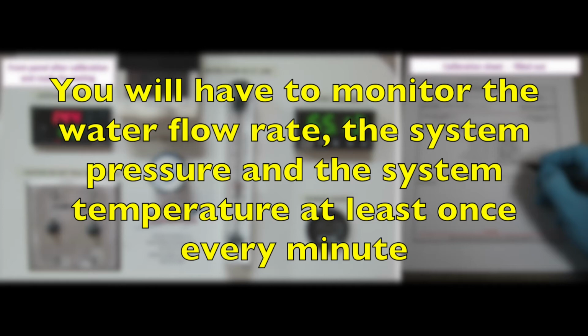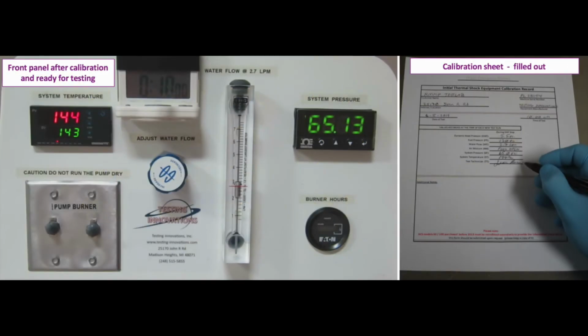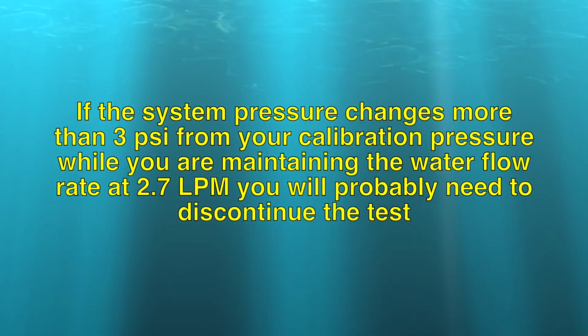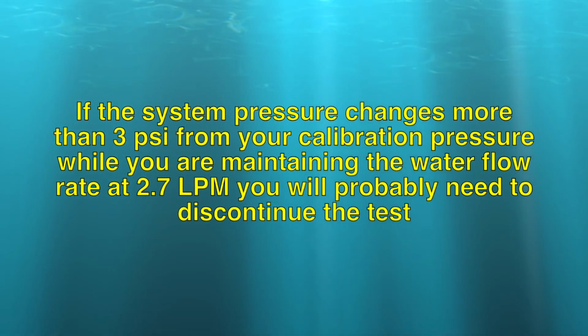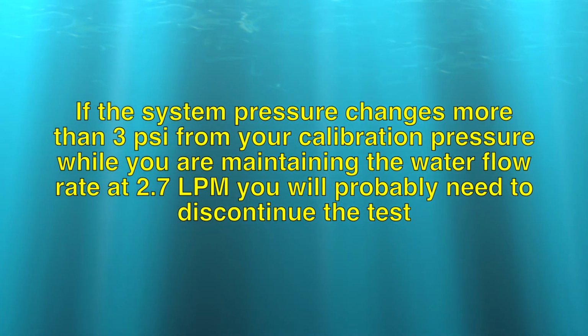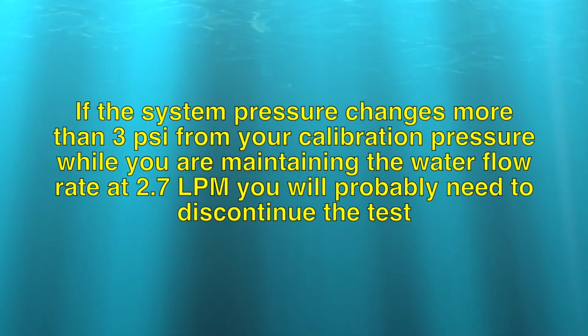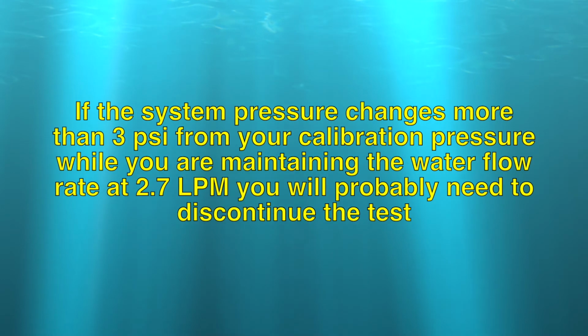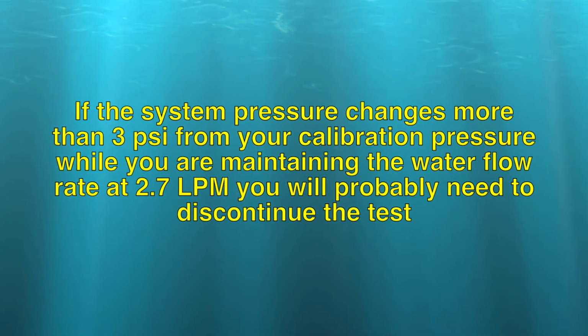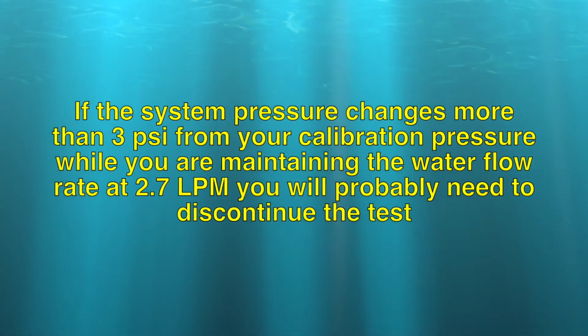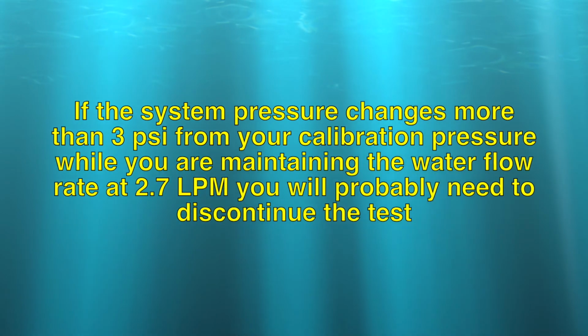The water flow rate will need to be adjusted periodically using the GO valve in order to maintain your individual target values. As a simple guideline, if the system pressure changes more than 3 psi from your calibration pressure while you are maintaining the water flow rate at 2.7, you will probably need to discontinue the test and restart the machine warm-up process or make a tiny fuel pressure adjustment.